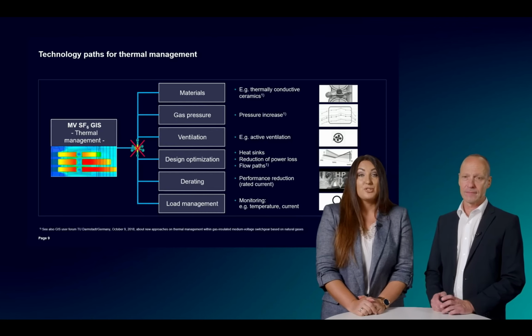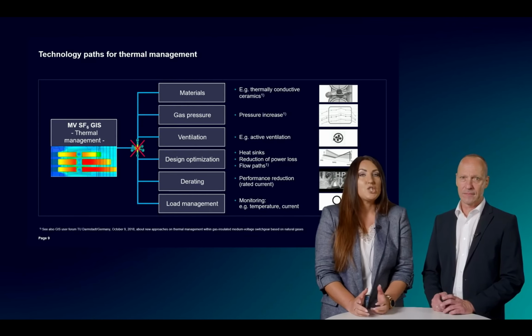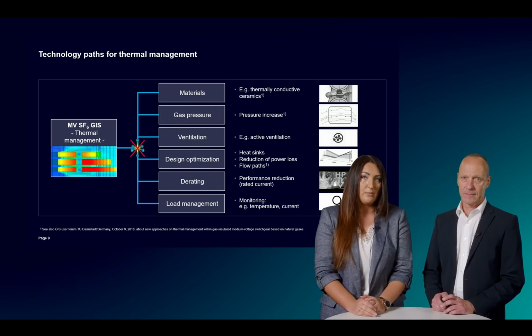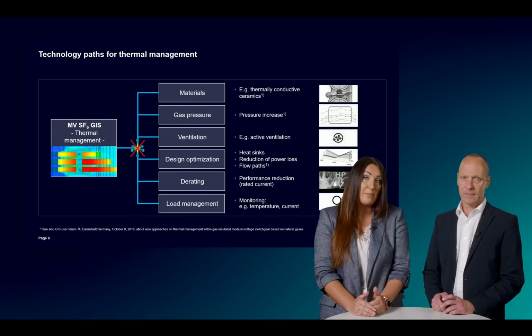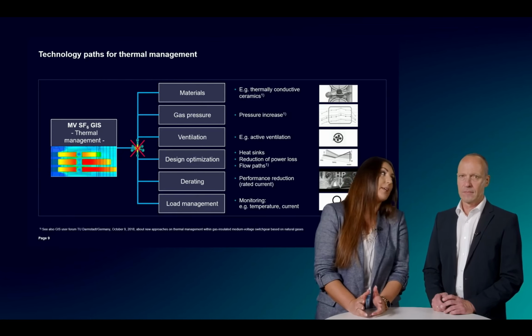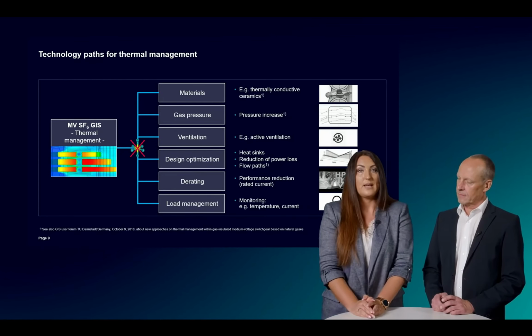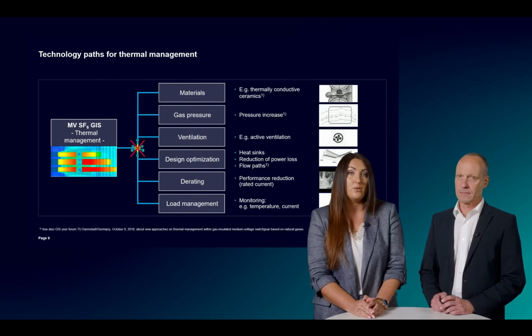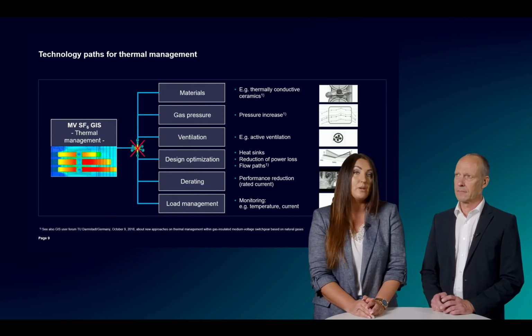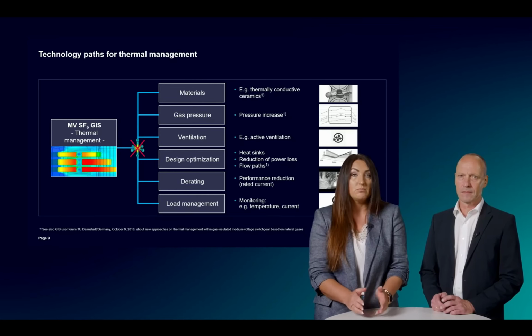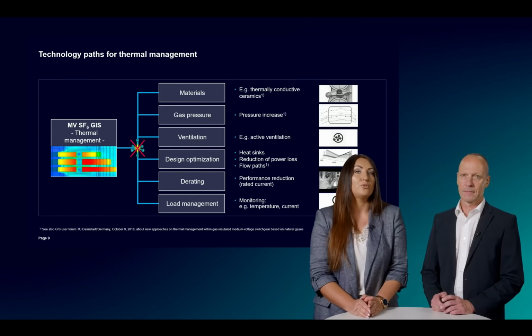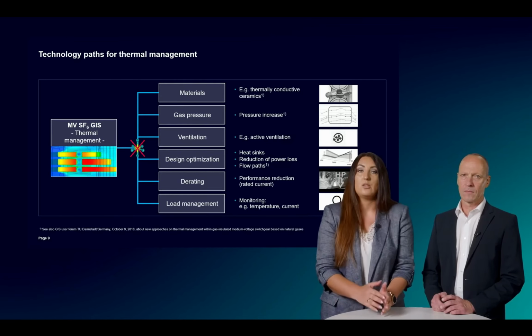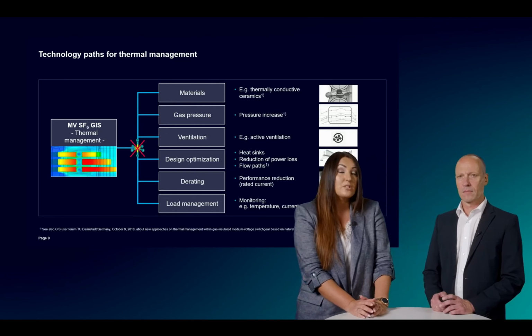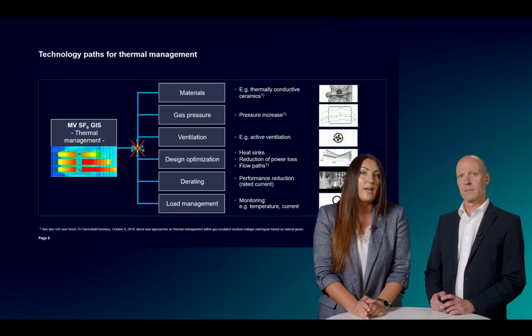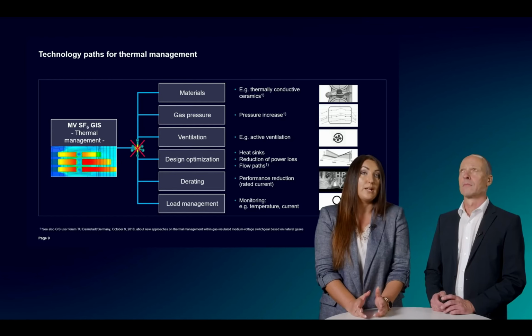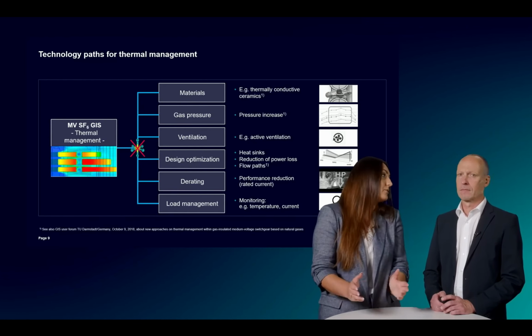Thermal management. When it comes to thermal management, a number of design changes and optimizations needed to be implemented in order to achieve the same ratings with the gas that has lower heat dissipation compared to SF6. One of the most prominent measures was to increase the pressure inside of the gas chamber. In addition, some different materials were used, heat sinks were introduced, and in some cases also active ventilation. For some typicals or panel typicals, there was a need for derating, a performance reduction, for rated current, for example.